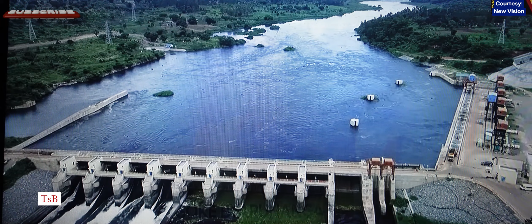When water is released from the reservoir to the intake, it falls through a penstock to the turbine. Each of the 6 installed turbine units is served by an independent intake inlet. From a head of 60 meters, each turbine unit requires at least a volume of 182,000 liters per second to rotate and generate 100 megawatts.